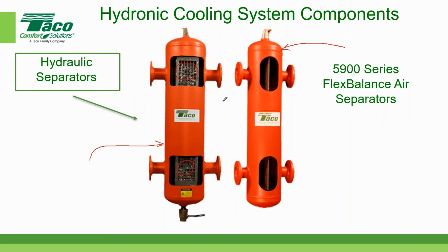So the one on the right will allow air to escape. The one on the left will allow air to escape, but also will allow you to collect dirt at the bottom with this blowdown valve and get rid of the dirt. So the one on the left is good for both air and dirt. Both of these are separating the primary from the secondary piping system. So that's another important component in a system.